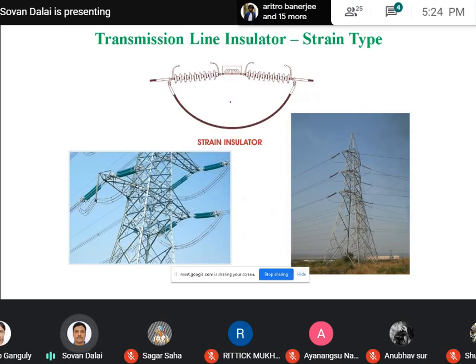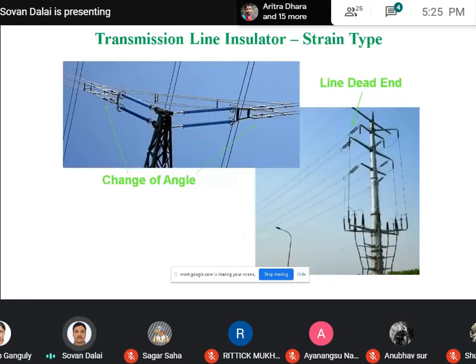And you see, this is one of the applications of the strain insulator. When this set of insulators is vertically mounted, they are called suspension insulators, and when the insulators are horizontally mounted, they are called strain insulators. The strain insulator is used where the line is changing its angle and where the line is terminated. In these two cases, we generally use the strain type of insulator, which is a combination of horizontally mounted insulators.